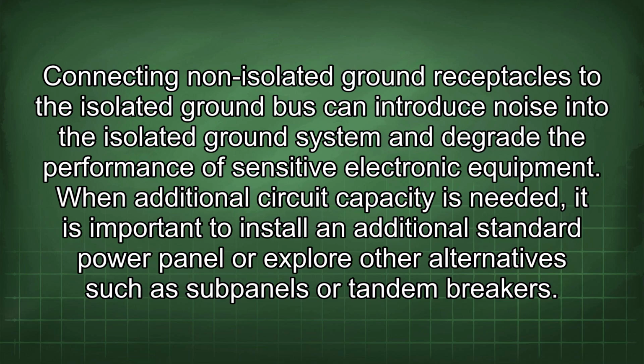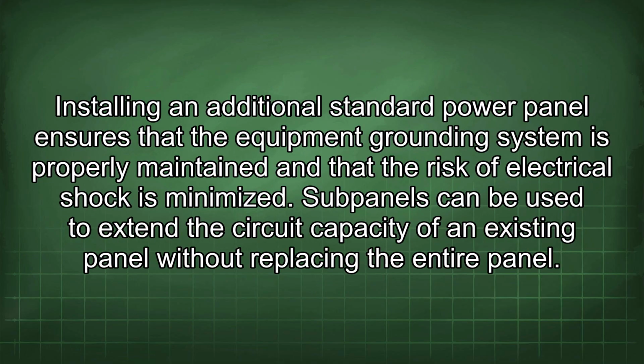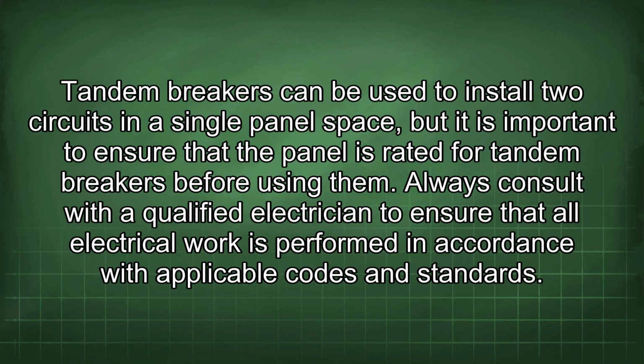When additional circuit capacity is needed, it is important to install an additional standard power panel or explore other alternatives such as subpanels or tandem breakers. Installing an additional standard power panel ensures that the equipment grounding system is properly maintained and that the risk of electrical shock is minimized. Subpanels can be used to extend the circuit capacity of an existing panel without replacing the entire panel. Tandem breakers can be used to install two circuits in a single panel space, but it is important to ensure that the panel is rated for tandem breakers before using them.